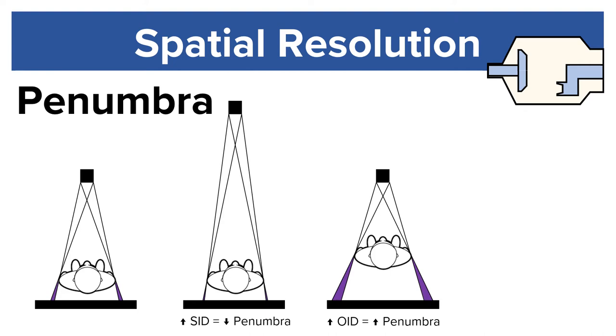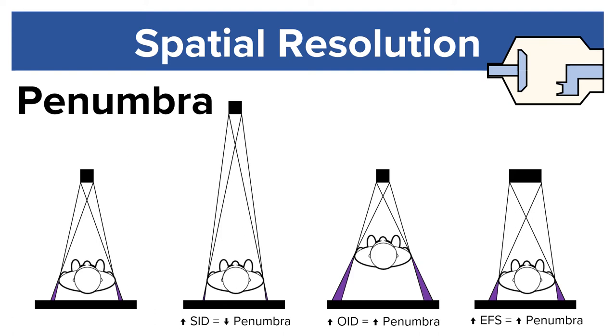What is penumbra? Penumbra is the area of unsharpness around an object. If you increase SID, you'll decrease penumbra. If you increase OID, you'll increase penumbra. And if you increase effective focal spot, you'll also increase penumbra.